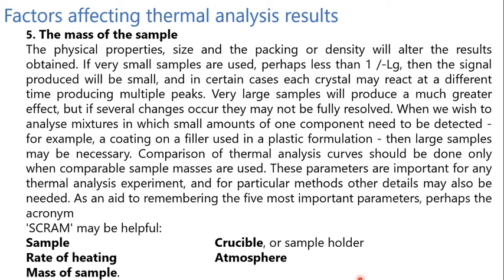Then the next factor is the mass of the sample. The physical properties, size and the packing or density will alter the results obtained. If very small samples are used, perhaps less than 1 milligram, then the signal produced will be small and in certain cases each crystal may react at a different time, producing multiple peaks. A very large sample will also produce a much greater effect, but if several changes occur, they may not be fully resolved.